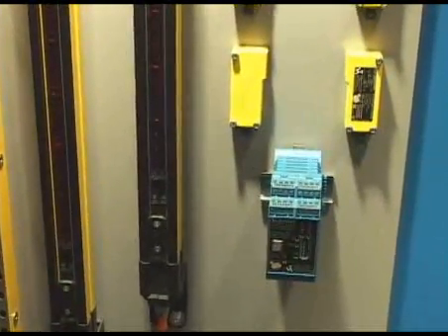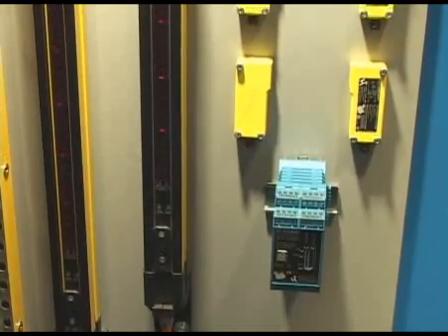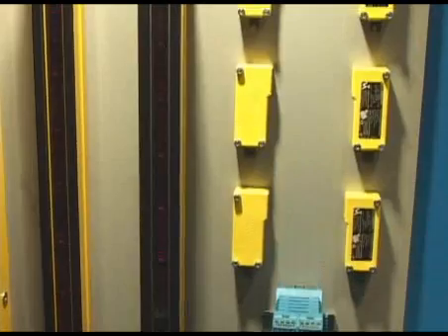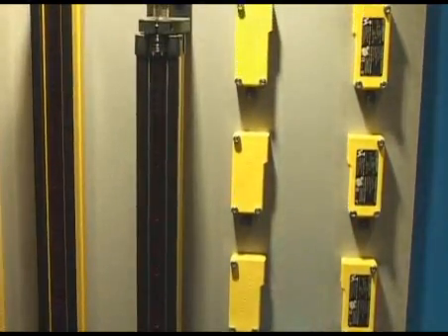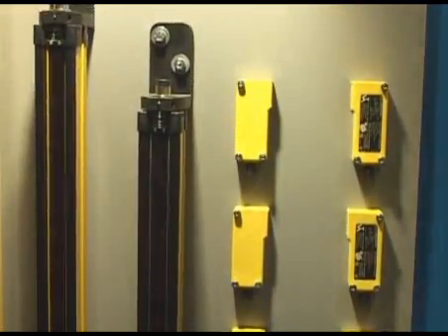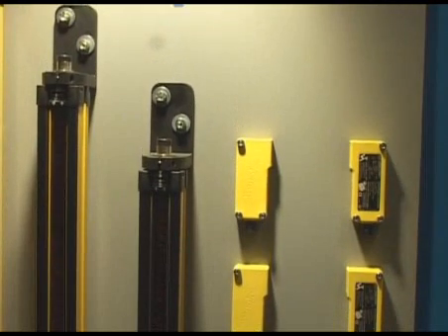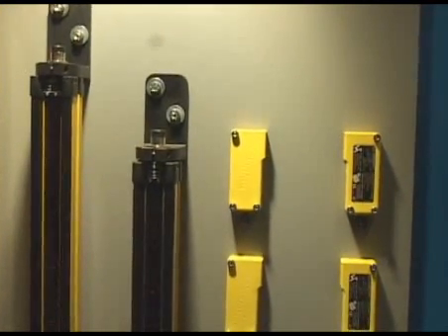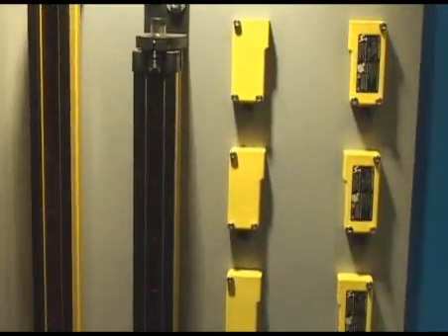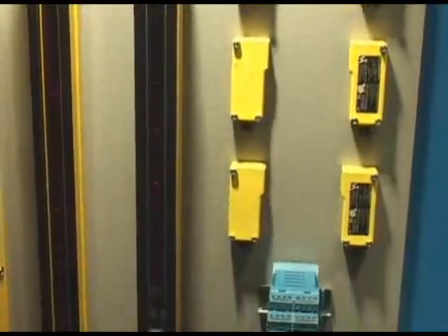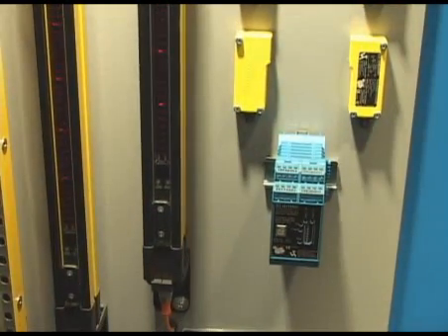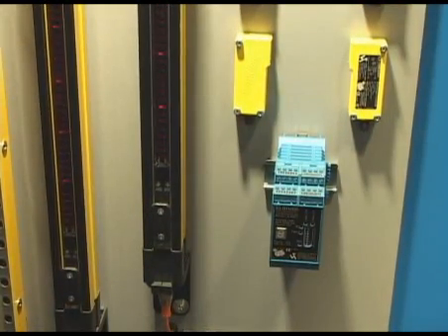Some of the functions and features that we have with the safety light curtains are muting, we have fixed blanking, we have float blanking, we have auto float blanking, we also have cascading where we can connect up to five sets of light curtains in series, and we also have continuous self-checking within our light curtains. We have finger and hand protection, and that's pretty much of our overview for our safety product line.